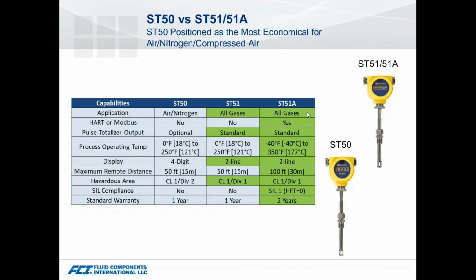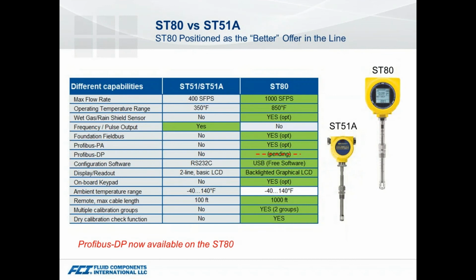Stepping up to the ST51A, now I'm getting the bus capabilities, a little bit better temperature capability, and I can drive the electronics a little bit further, 50 feet to 100 feet. This is one product where we've actually taken it to Exida and had an FMEDA performed, so we know what the failure rate data is for IEC 61508 and 61511. Stepping up from the 51A, which is more of our economical scenario, we go to the ST80 in the group, and there's quite a bit of difference here. We have flow elements with higher temperature capabilities, flow range capabilities, the bus capabilities, and we can go up to 1,000 feet between the flow element and the remote electronics.